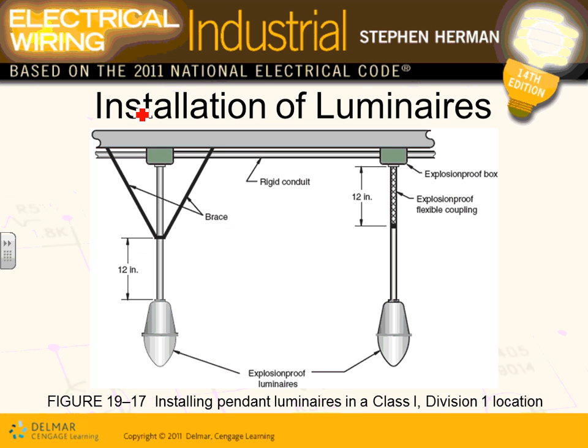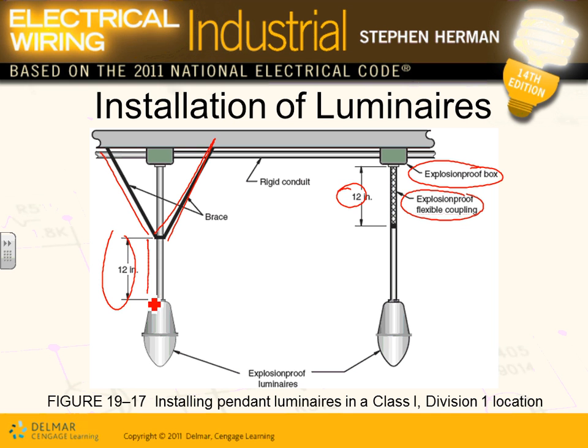When you have a luminaire in a Class 1 Division 1 location, if it goes more than 12 inches, you either have to support it with explosion-proof flexible couplings, as they call them, with an explosion-proof box, or you have to have the brackets. Can you see the brackets that go in there? The only thing that you don't need to support is the last 12 inches.